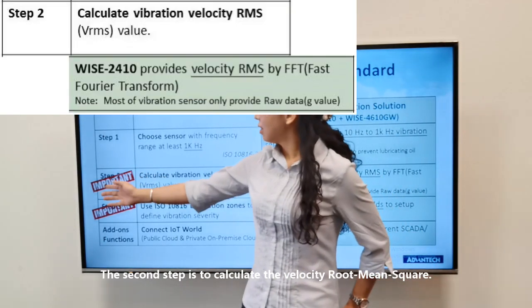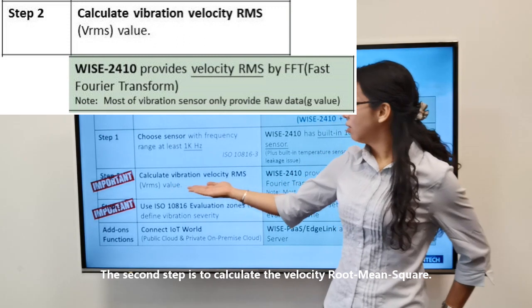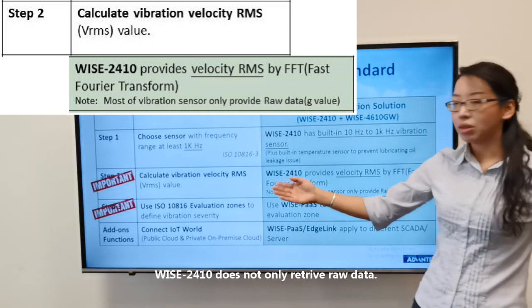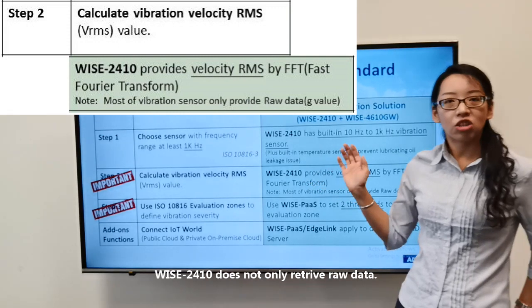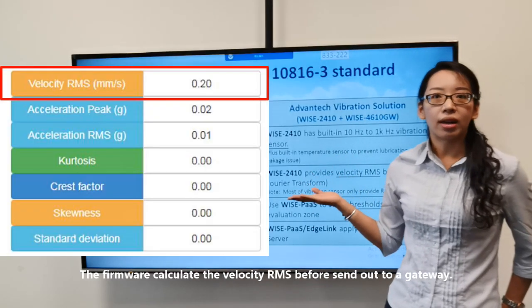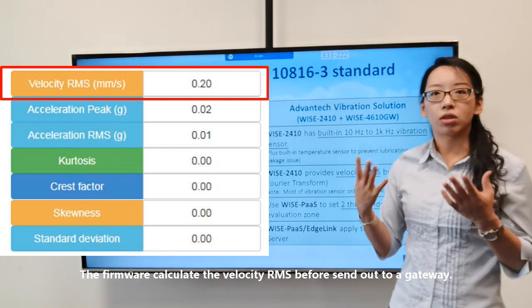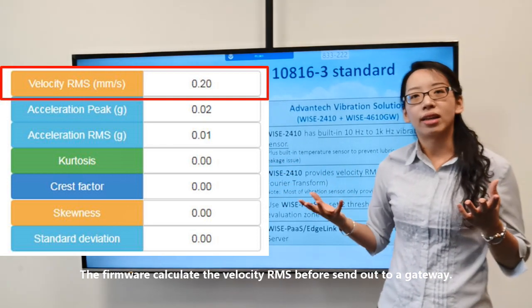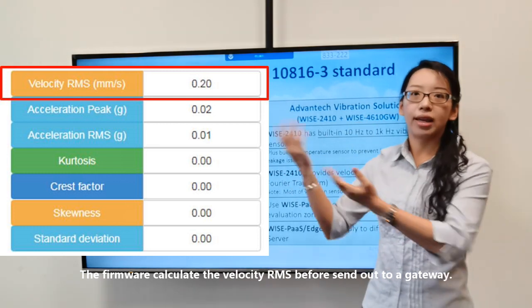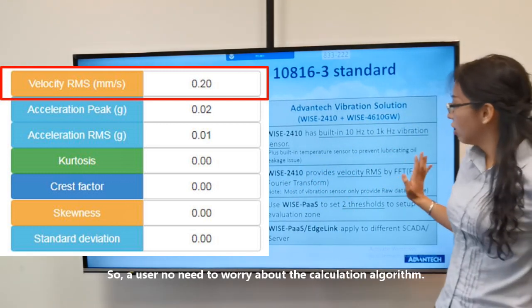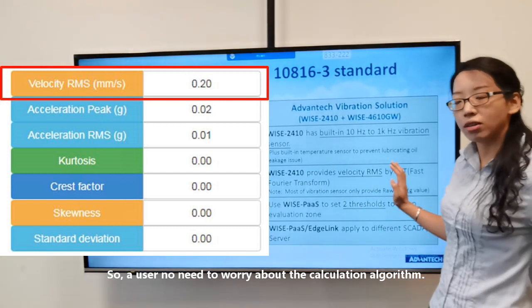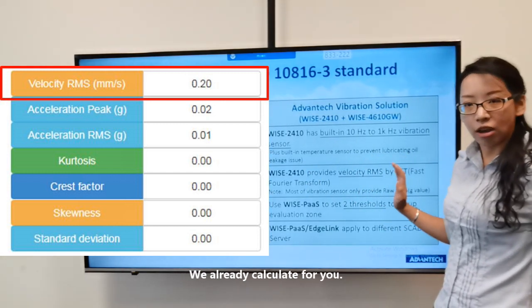The second step is to calculate the vibration velocity RMS. WISE2410 does not just retrieve raw data — the firmware will help users calculate the velocity RMS before sending it out to the gateway. So users don't need to worry about this calculation part; we already calculate it for you.